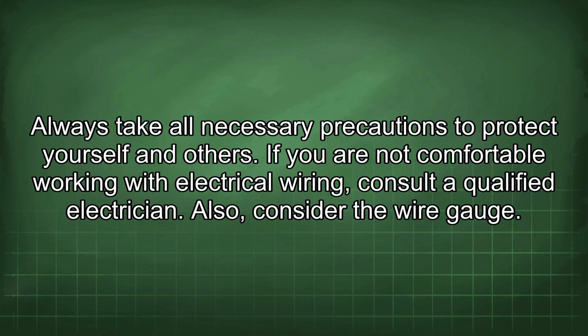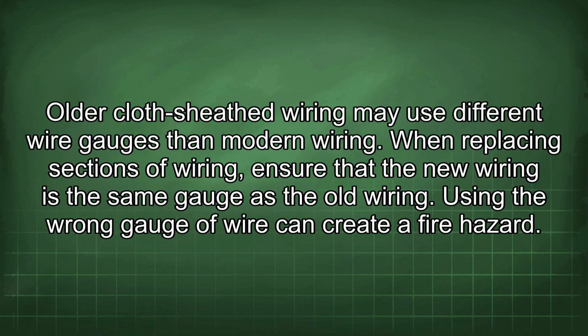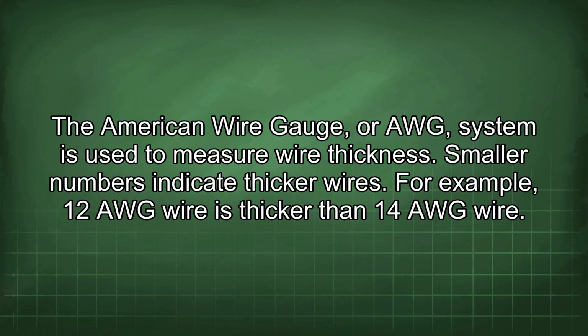Also, consider the wire gauge. Older cloth-sheathed wiring may use different wire gauges than modern wiring. When replacing sections of wiring, ensure that the new wiring is the same gauge as the old wiring. Using the wrong gauge of wire can create a fire hazard. The American wire gauge, or AWG, system is used to measure wire thickness. Smaller numbers indicate thicker wires. For example, 12 AWG wire is thicker than 14 AWG wire.